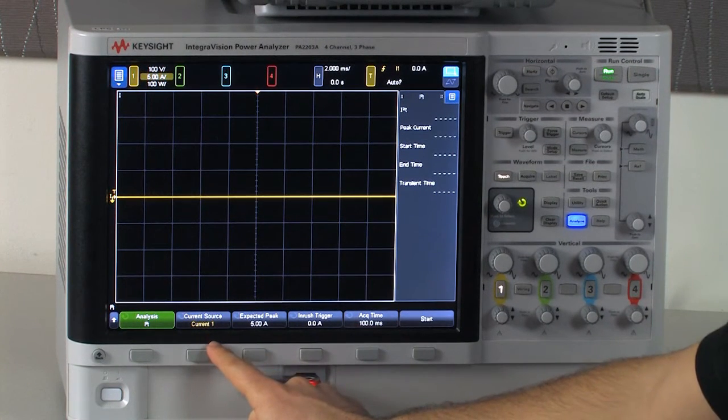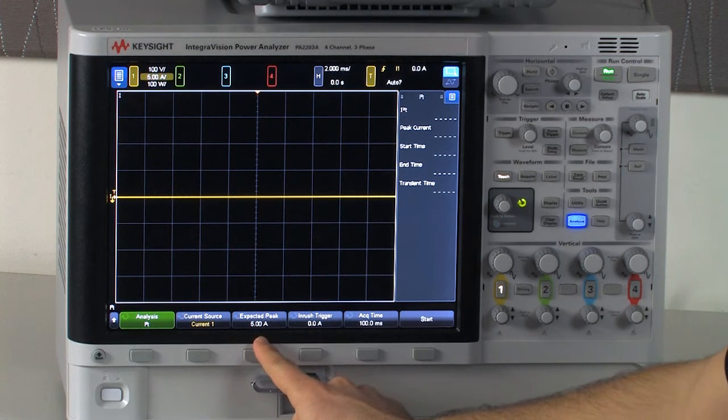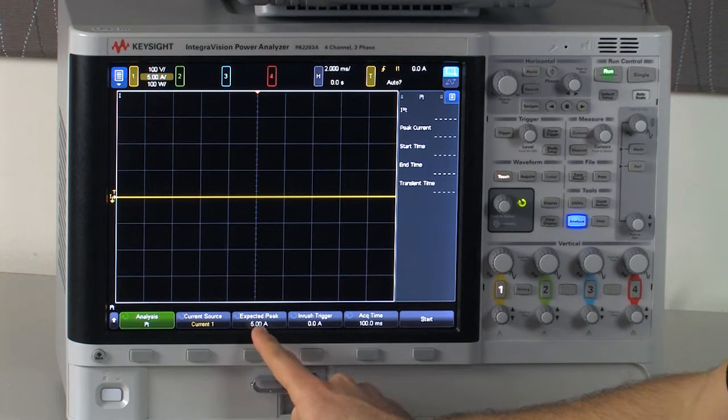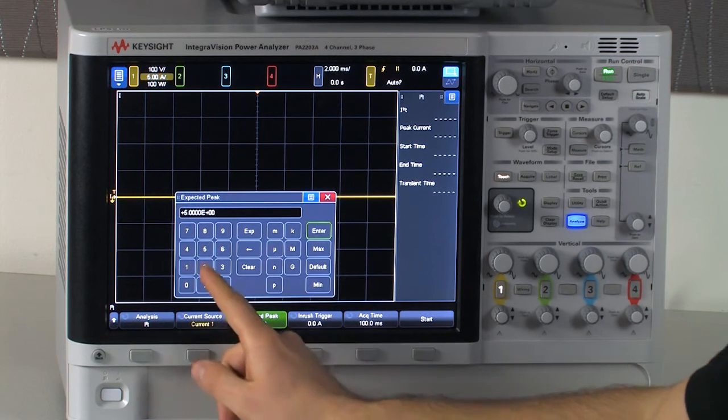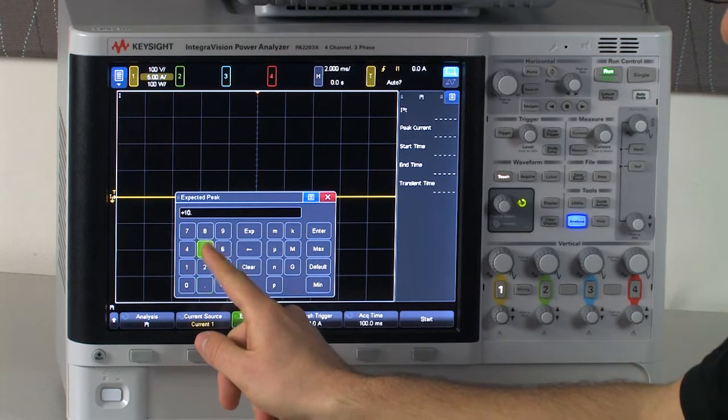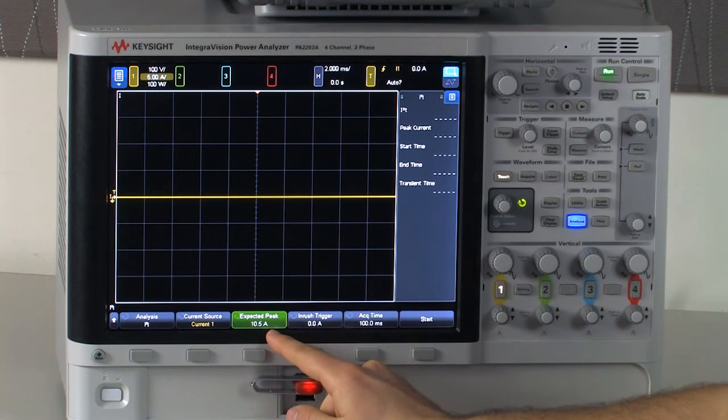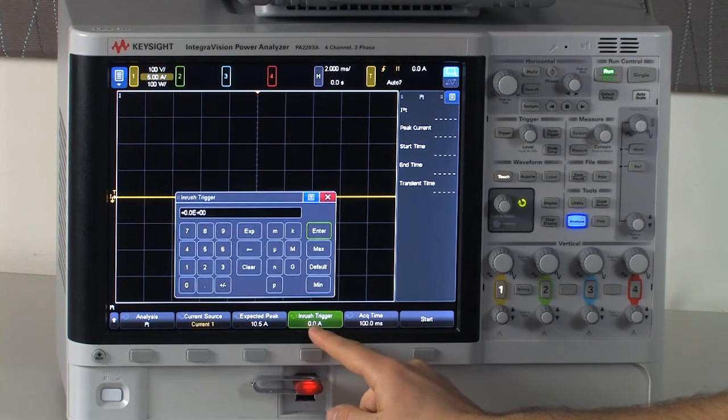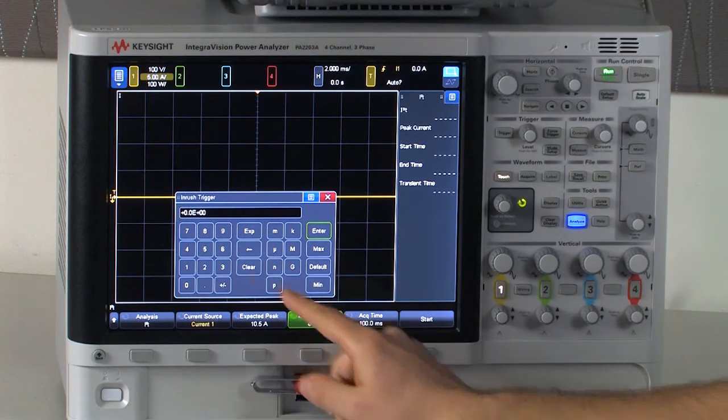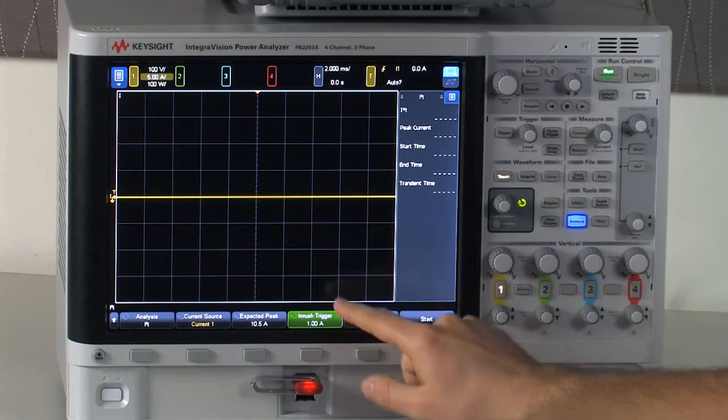The current source is what we'll be doing the I-squared-T test on. The expected peak will be at or above the inrush current peak that you're expecting. Since I have a 10 amp peak, I'll set that to 10.5 just to be a little bit higher and to set the hardware range. The inrush trigger is the current level which the test will trigger off of. I'll set that to 1 amp.